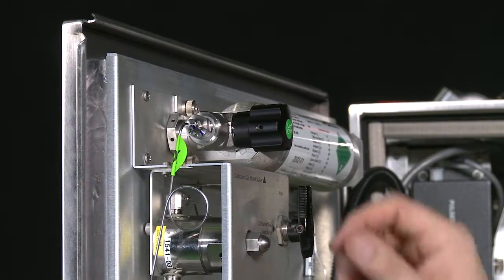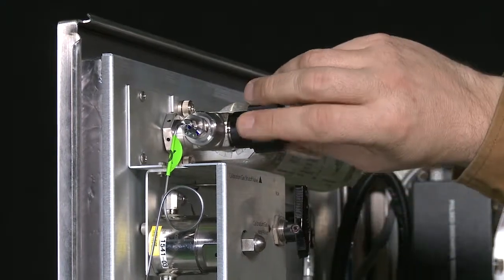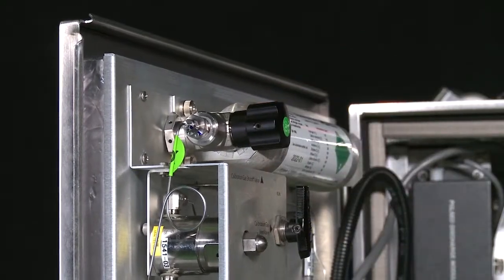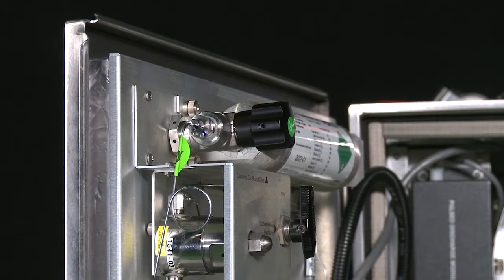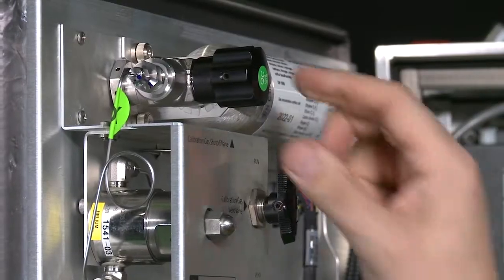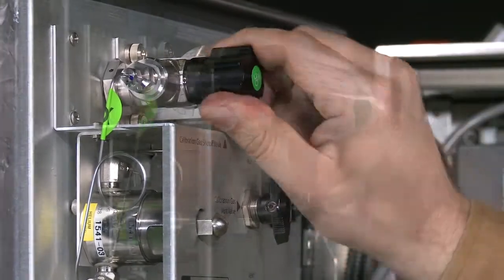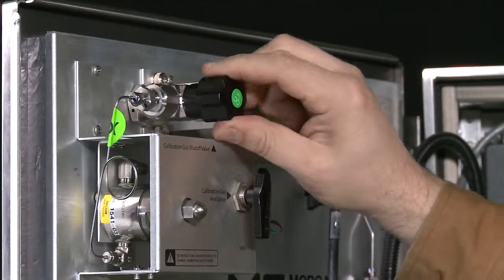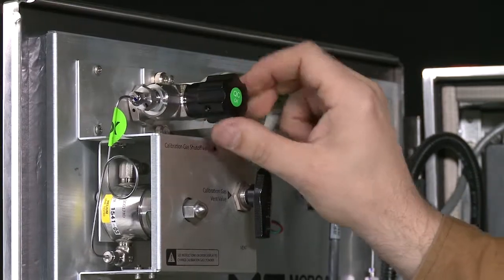Open the calibration gas shutoff valve 1/4 of a turn and reclose as quickly as possible. Wait 5 seconds for the gas to escape. Repeat the previous step a second time, then turn the vent valve to run. Open the calibration gas shutoff valve about 1 full turn.